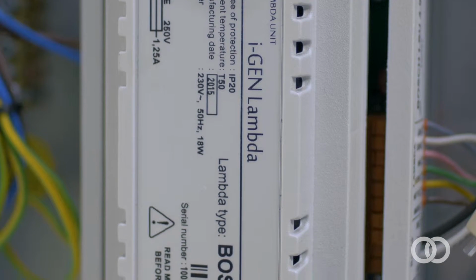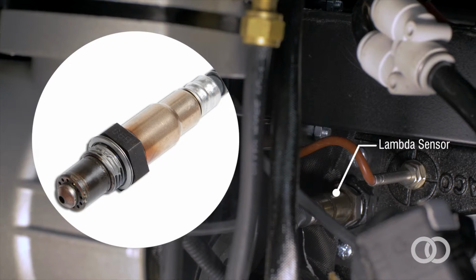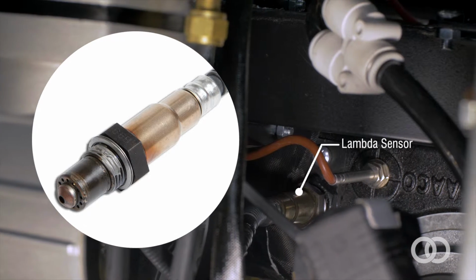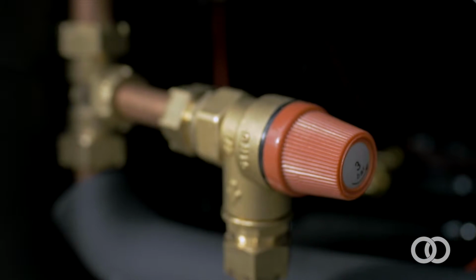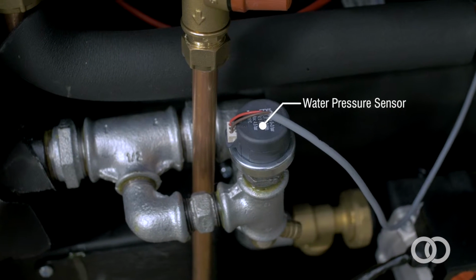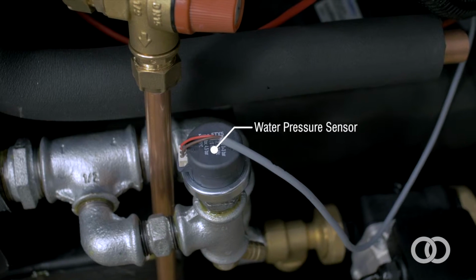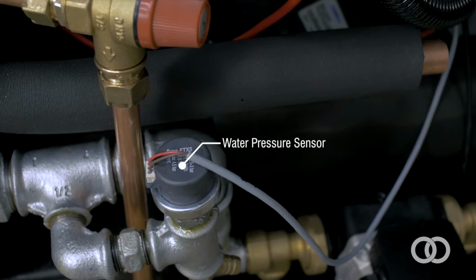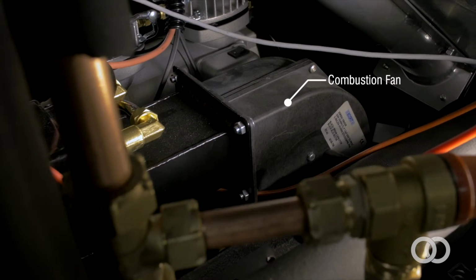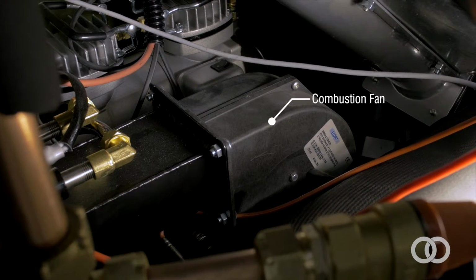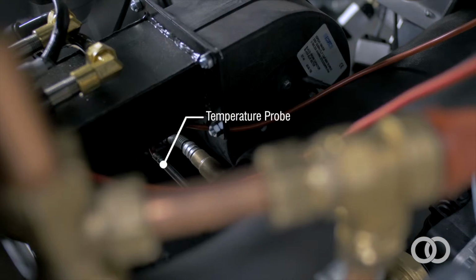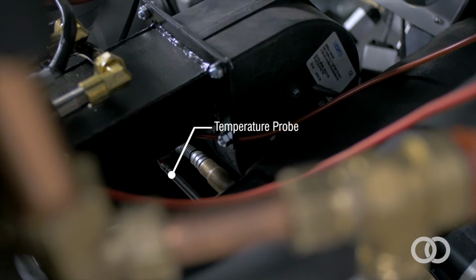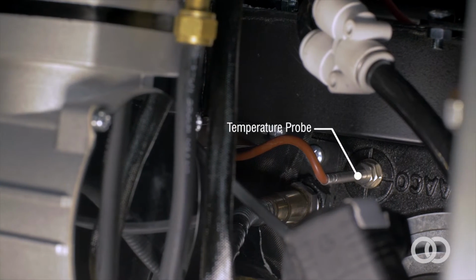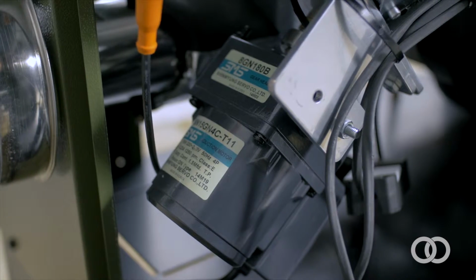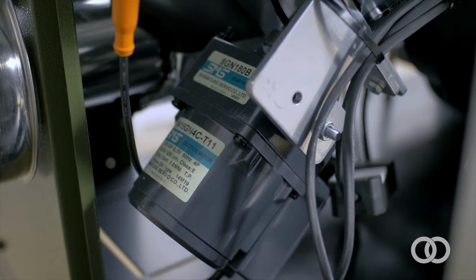All W-Compact boilers have lambda sensor and controller as standard, ensuring even greater efficiency and quality combustion. A pressure relief valve fitted as standard and plumbed. Water pressure sensor which alarms if water pressure is less than 1/4 bar and exceeds 2 3/4 bar pressure. Combustion fan ensuring greater quality combustion compared to single exhaust fan systems. Here you can see the temperature probe that measures the exhaust gas temperatures as it exits the boiler. Here is the auger motor that drives the auger flight.